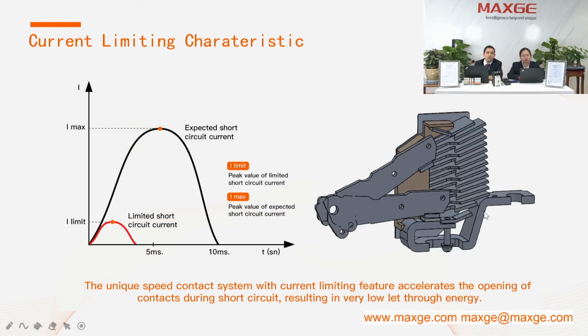In this slide you can see our MCCB has current limiting characteristics. What does it mean? It means that during a short circuit condition the breaker should limit the current to protect the wiring and the final load. Our MCCB has a unique design of the moving contact, the fixed contact and the arc chamber, which limits the current, and the current will not reach the peak current. It will be maybe one third of the peak current. So it will limit the breaking current, and finally the wiring and the load will be protected.